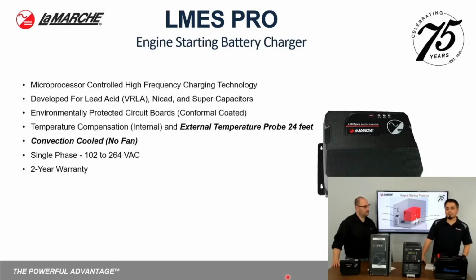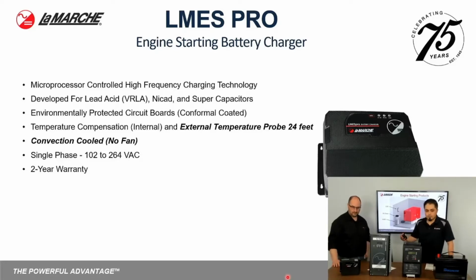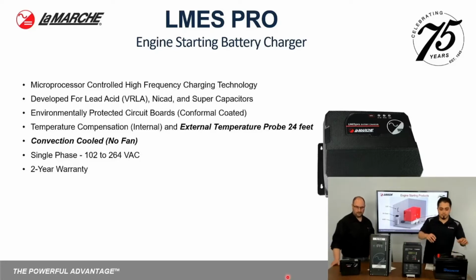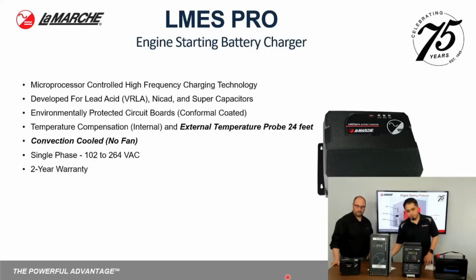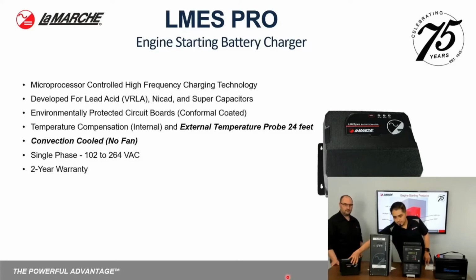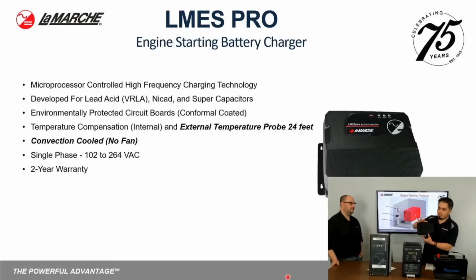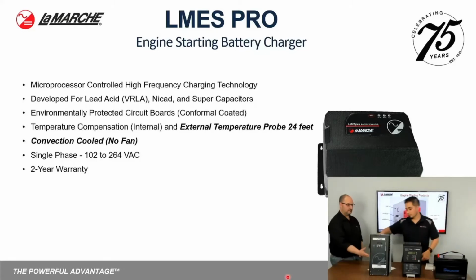We do have temperature compensation, an internal temp probe to compensate the voltage if it is either too hot or too cold, and we have the option of adding external temperature probes. This would be ideal if you were to put it on your battery terminals themselves. This is also convection cooled. As you can see, there is no heatsink and no fans on the front, but in the back there is a heatsink to help with the cooling of this device.